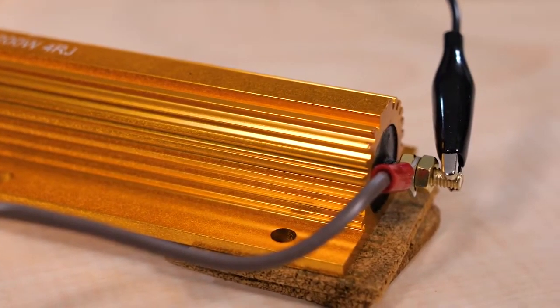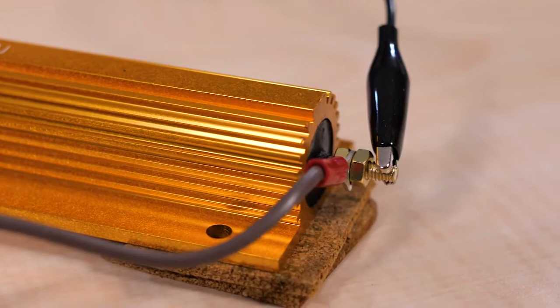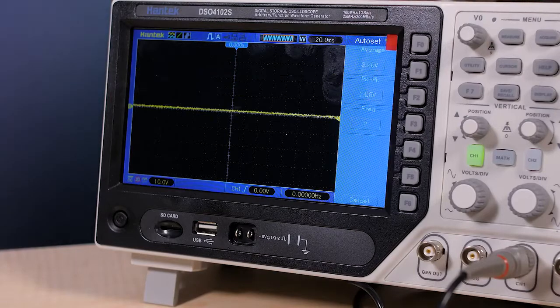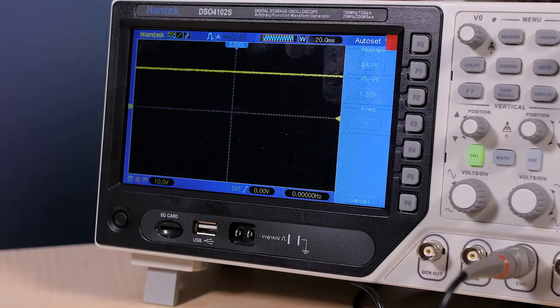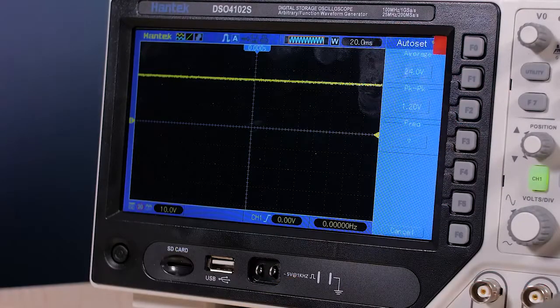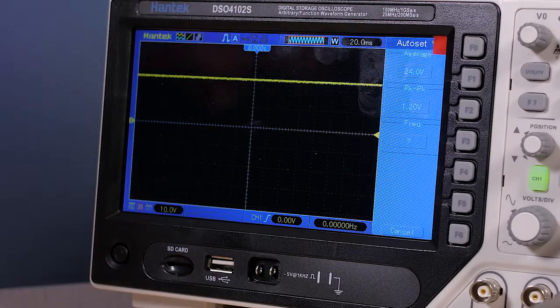There are plus and minus remote control pins on the connector, as well as plus and minus remote sense pins. The two remote pins implement a remote control feature used to turn the output voltage on or off. The point of this feature is to reduce input power if the system is in idle or sleep mode. This feature is useful for cycling the output power without having to cycle the input power. That helps reduce the AC inrush current and extend the life of an external circuit breaker or input fuse if the supply is in a system that uses them.